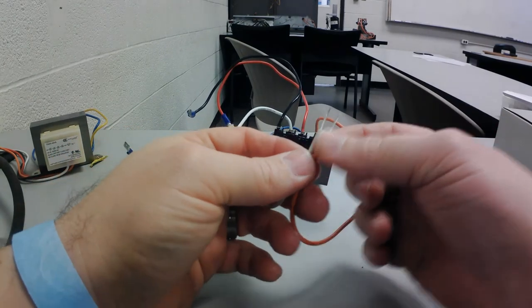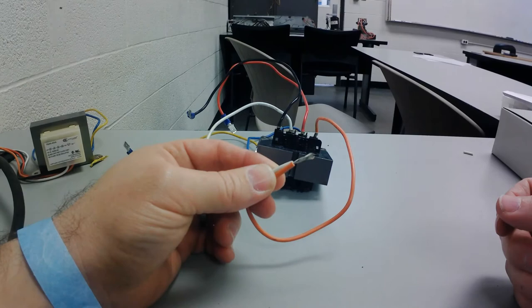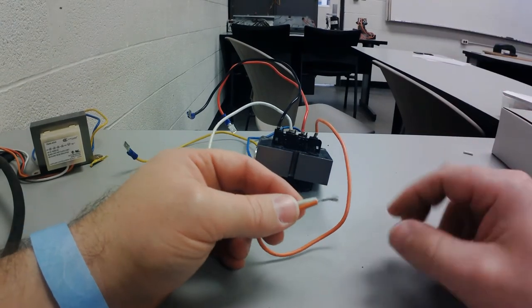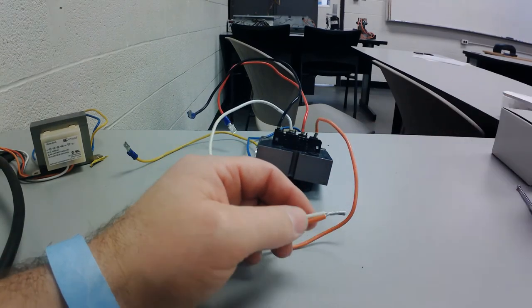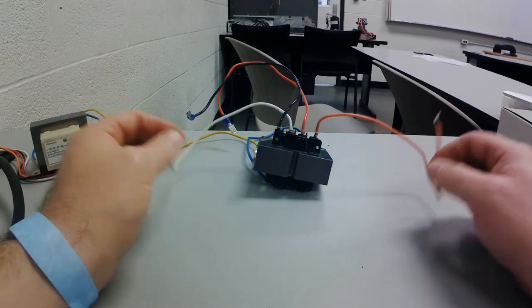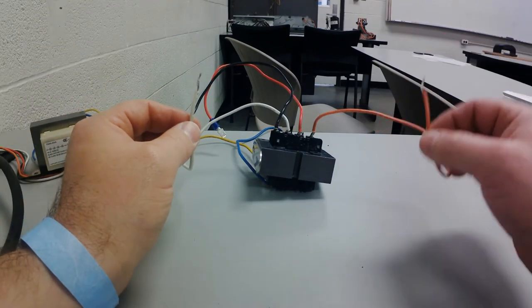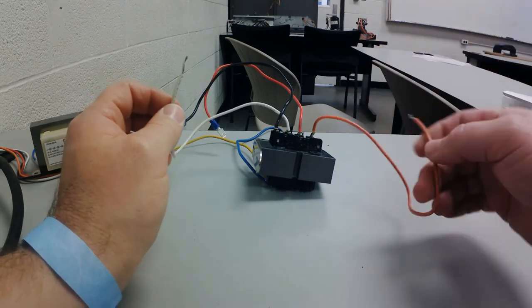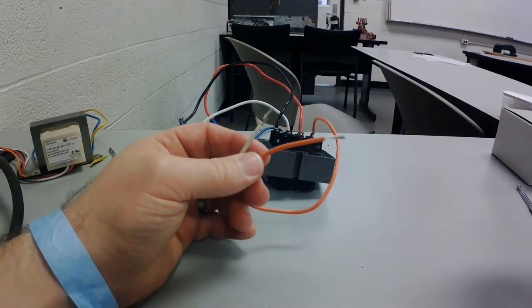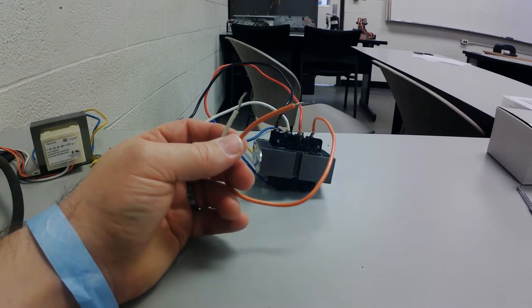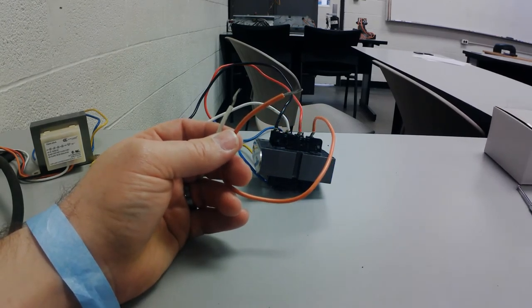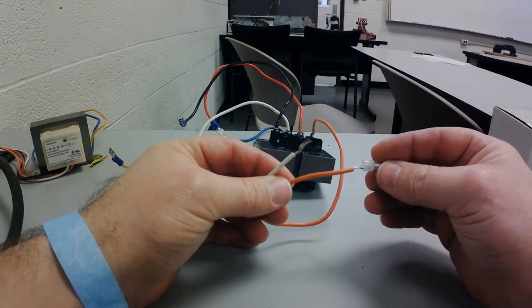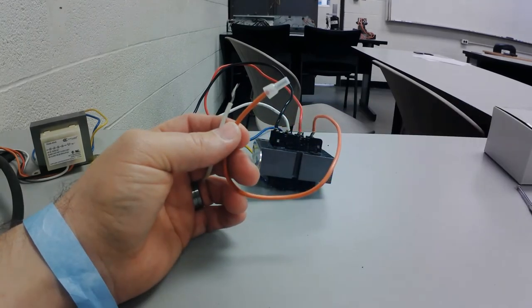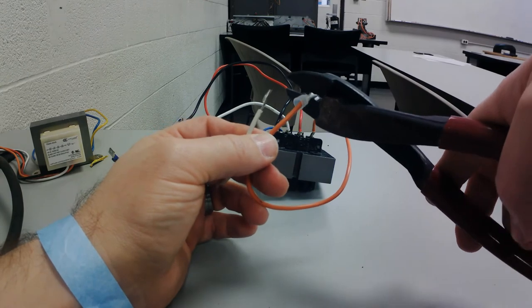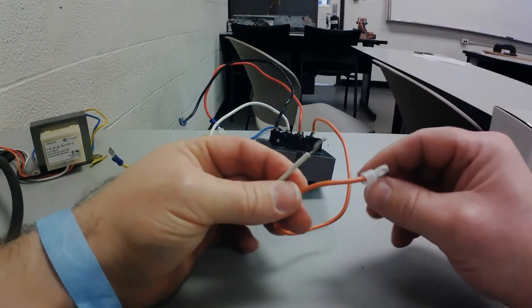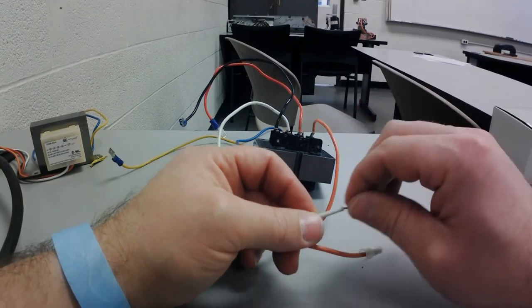You do not take two of these wires and connect them together. That will literally melt that insulation and catch it on fire, I've seen. So you wanna be careful. Multi-tap transformers, the same as a multi-speed PSC motor, use one wire at a time, and the unused go somewhere like a park terminal, or they get dealt with in an individual wire nut or a cap that you have here. So you don't want to use them. You don't want to hook them back up because they will cause you some problems, and it will not take very long. So you just take a little cap like this, and you put it on the wire that you have, and you take your crimpers, and you crimp it, and do that for your unused. So hopefully that helps. If you have any questions, let me know.